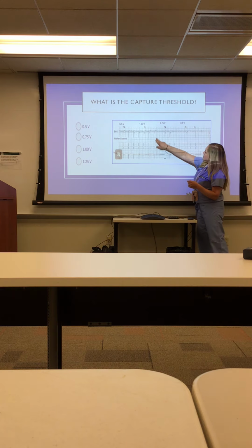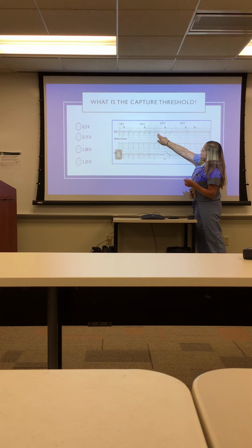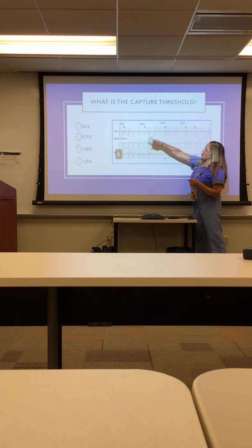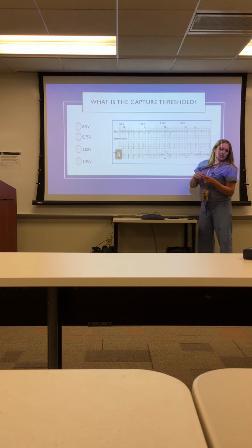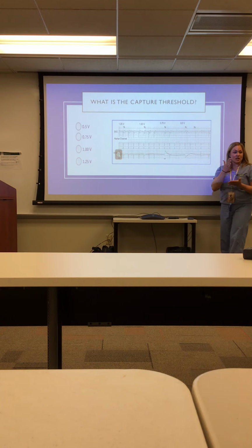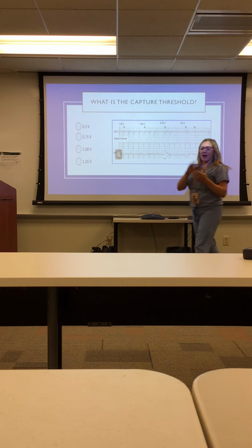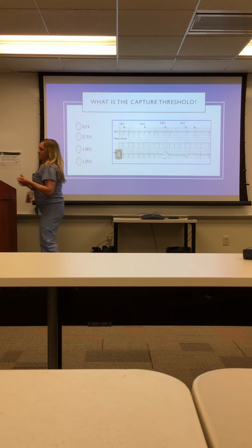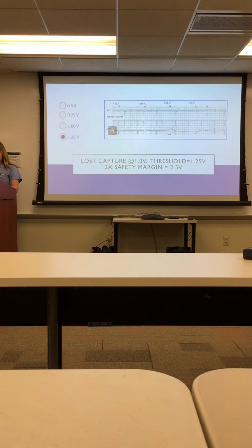So in this case, it looks like we lose capture here, and we see an intrinsic beat come through. So in this case, the threshold is sitting right around 1, but we always bump it up another quarter volt. So we make 1.25 our threshold. Now, after that, you'll want to add on that 2-times safety margin. So with 1.25, you would then want to program the device to 2.5. Does that make sense, to give it enough of that margin there?